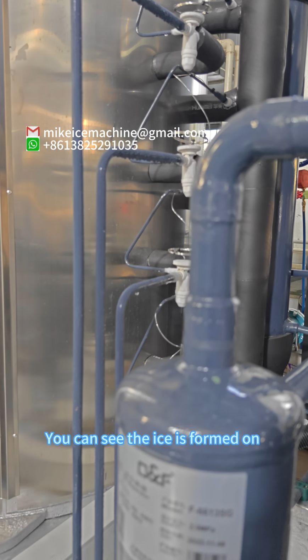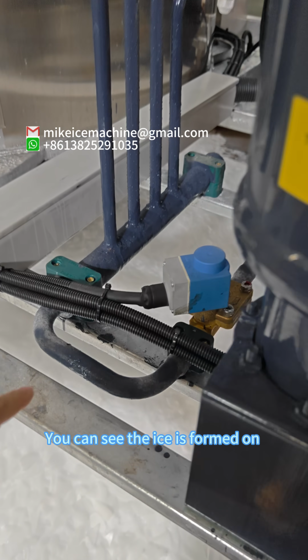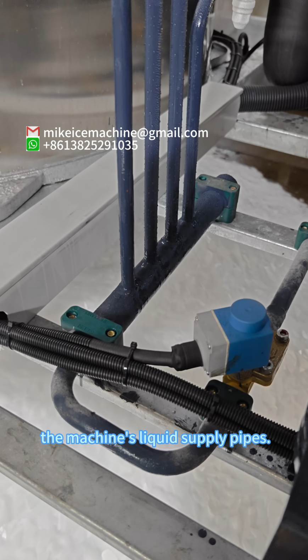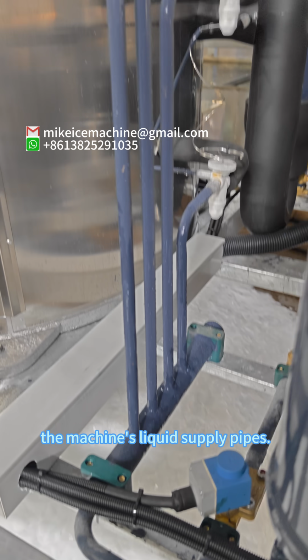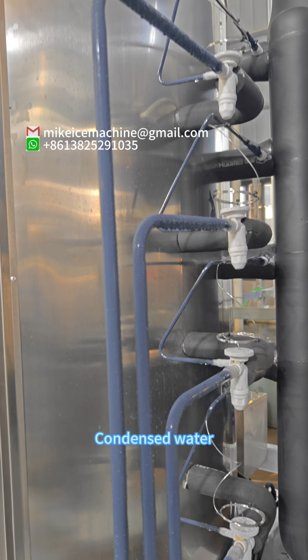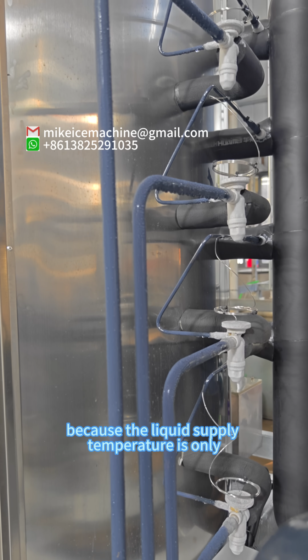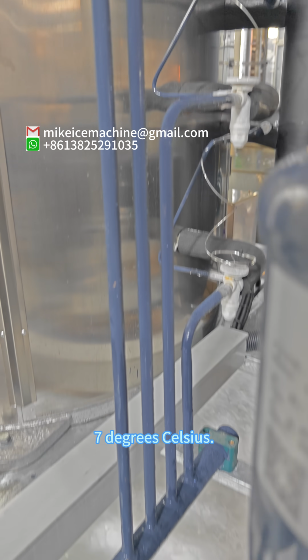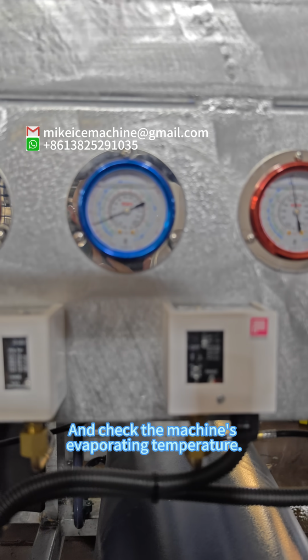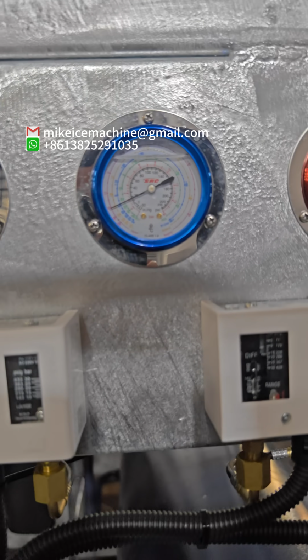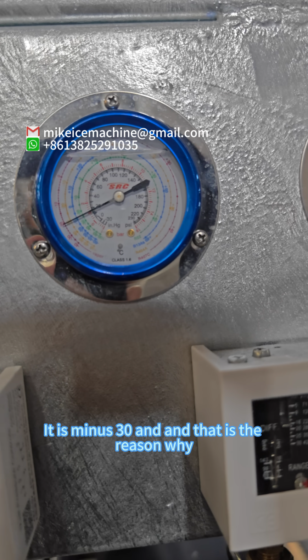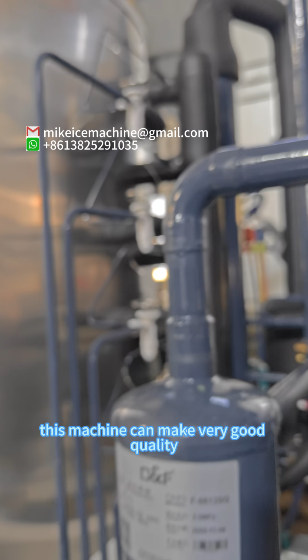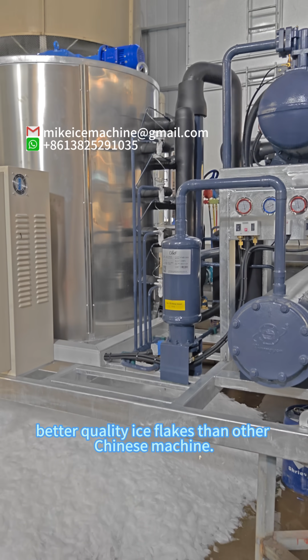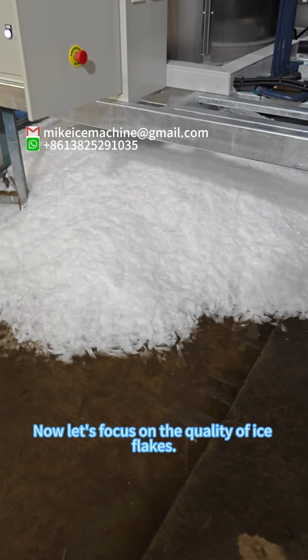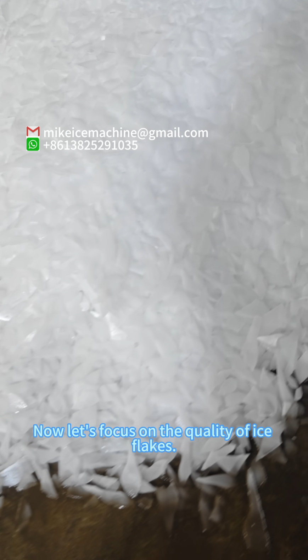You can see the ice is formed on the pipe of the machine's liquid supply pipes and the condensed water, because the liquid supply temperature is only 7 degrees Celsius, and the machine's evaporating temperature is minus 30. That's why this machine can make better quality ice flakes than other Chinese machines. Now let's focus on the quality of the ice flakes.